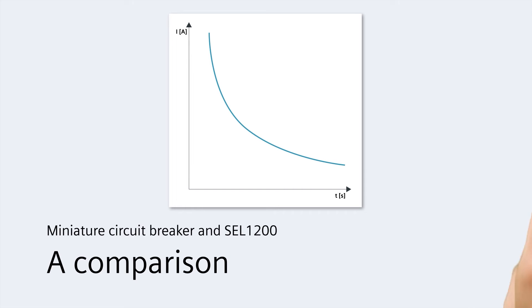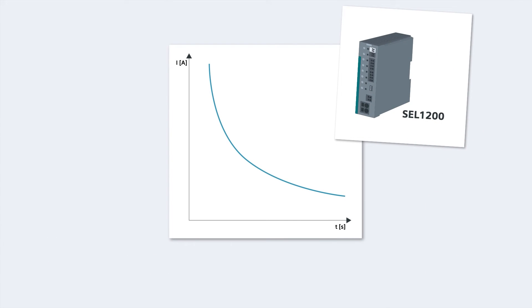Let's take a look at the SEL1200. As you can see, when a fault occurs, the SEL1200 trips much sooner. It also responds to a much lower current, meaning that the other loads are much less affected and the voltage dip is minimized.